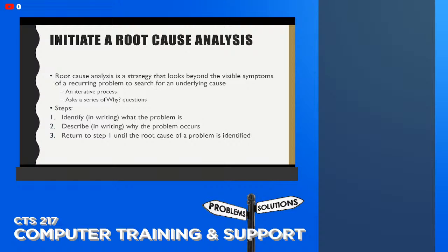Well, you could just replace it again. Chalk it up to bad hardware, faulty hardware. But you should probably be finding out why. Maybe if you look into it, you see, oh, there's water collecting. We're getting some condensation collecting on this duct in the ceiling, and it's dripping water down into the ventilation of the rack, and it's getting on the internals, and it's causing a short.